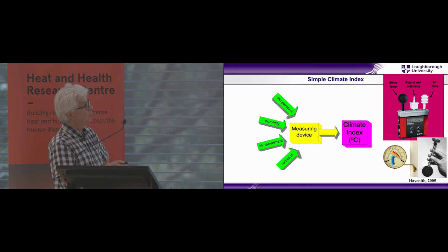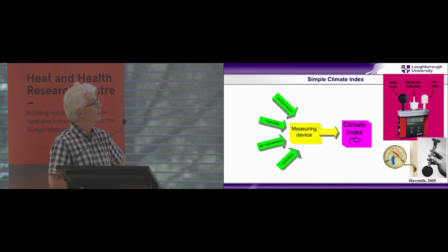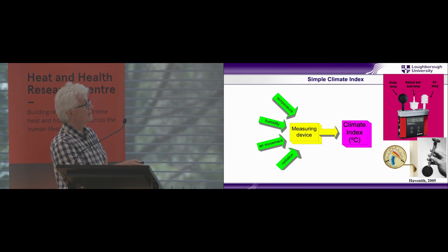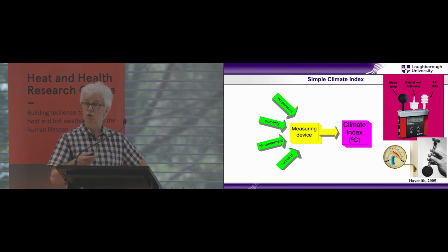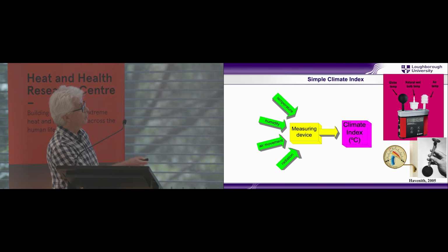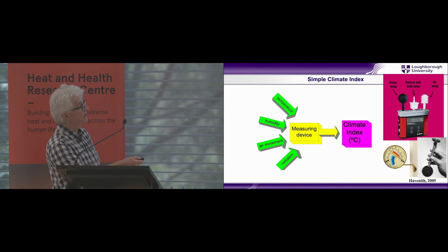The most well-known one probably is WBGT, the wet bulb globe temperature. And that has three sensors: air temperature, which is covered here or protected from radiation; a black globe, in this case quite a small one, which is sensitive to radiation, but also to wind, because if it heats up and you blow wind over it, it cools it down. So that's, again, what people tend to forget when they replace this with other things. And the really important one, which is the most important factor, accounts for 70% of the value, the natural wet bulb temperature.